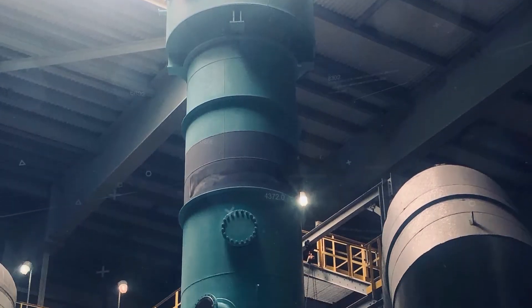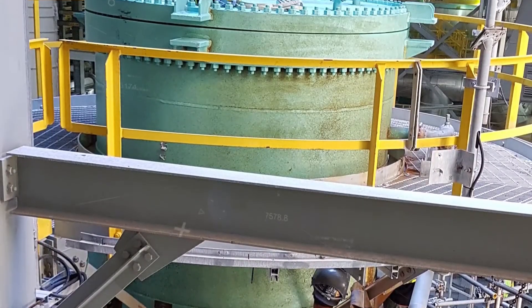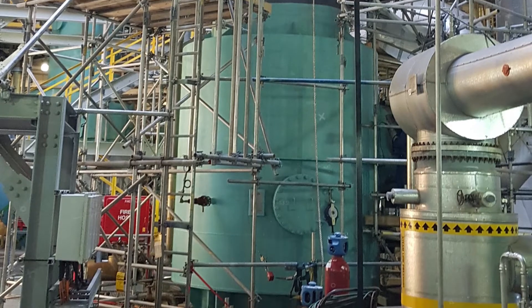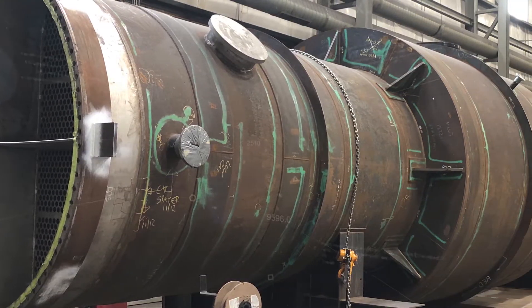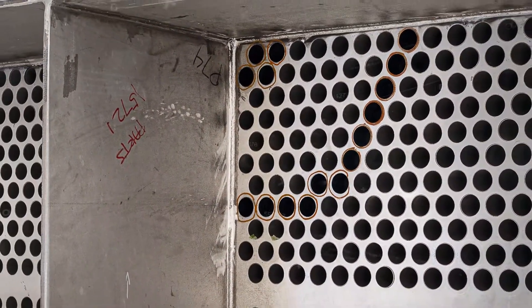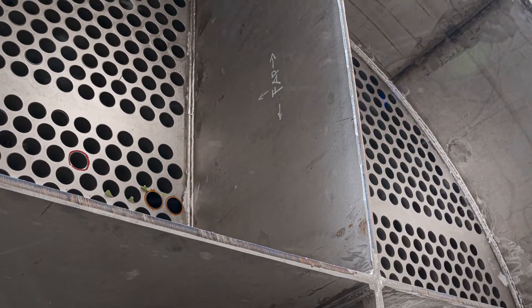The concept is simple, but designing and fabricating an exchanger to ASME standards can get quite complex. Some of the challenges in this project were that we were replacing two existing condensers, as the tubes and tube sheets of the existing condensers were corroding at a rapid rate. New alloys were selected for the replacements, and these new alloys introduced some design challenges that had to be overcome.